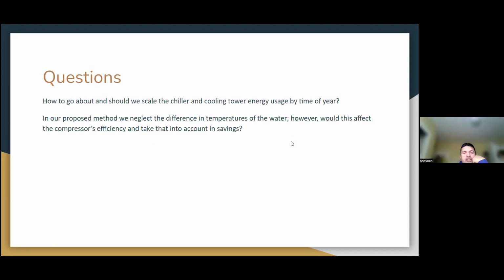Okay, so I'm going to take your second one because that's a quicker, simpler answer. Probably yes, but likely not much. You're absolutely right that the cooler the water used to cool a compressor, the more efficiently it works. However, there's a minimum floor to it. You're providing, let's say, 44, 45 degree chilled water to it, and the cooling tower, using the wet bulb rules, maybe giving it 75. The gain in efficiency between 75 and 44 might not be as much as if it were an air cooled compressor going from 100 degrees to 75.